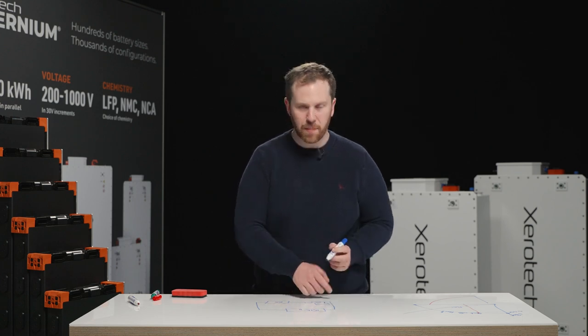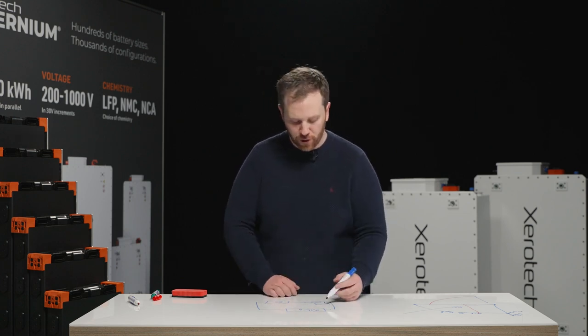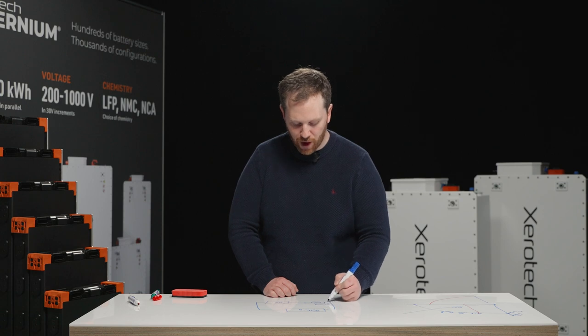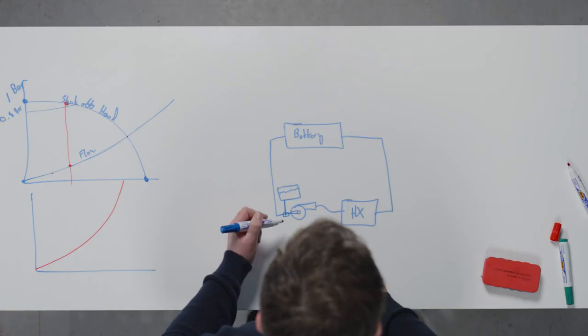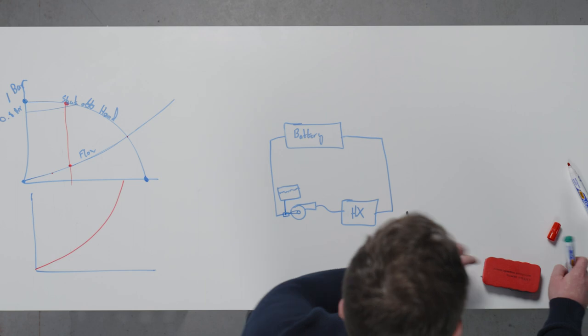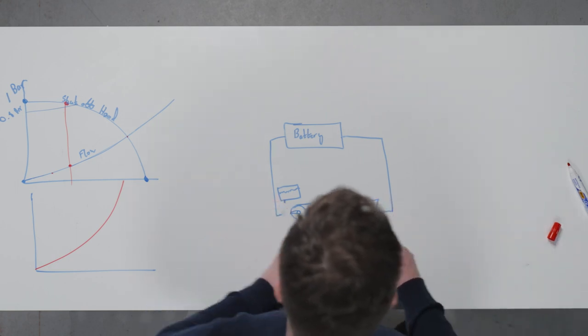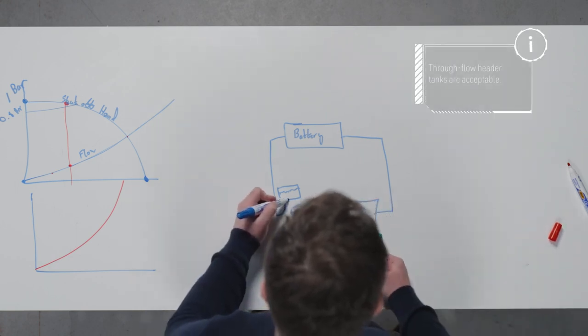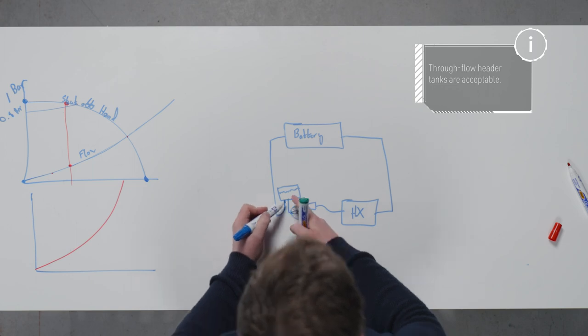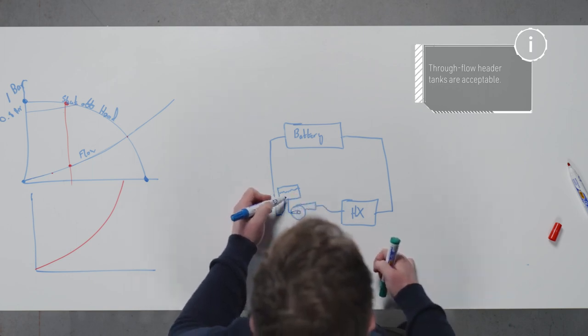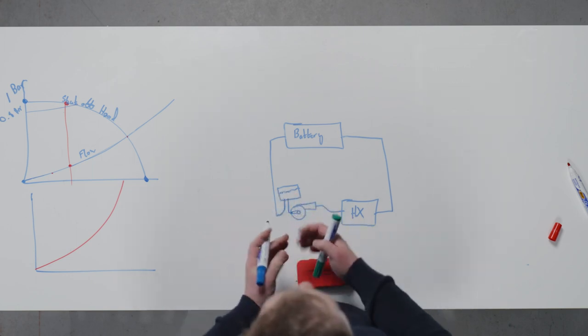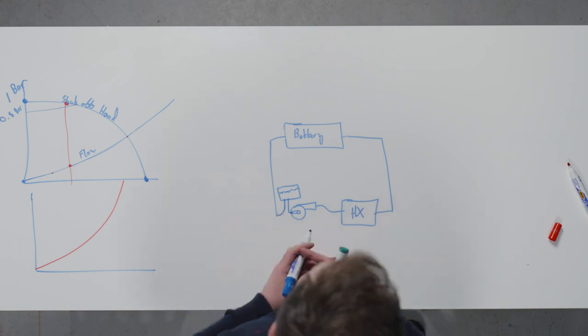Sometimes these header tanks might be through flow header tanks. So it's not just a column of water onto a T on a pipe here. It might actually flow through the header tank. And this is fine too. Both systems are acceptable. By flowing through that header tank, it's much more effective at catching air and bubbles in the system. So either is acceptable.